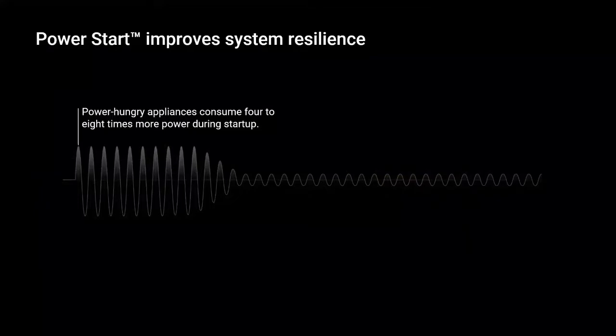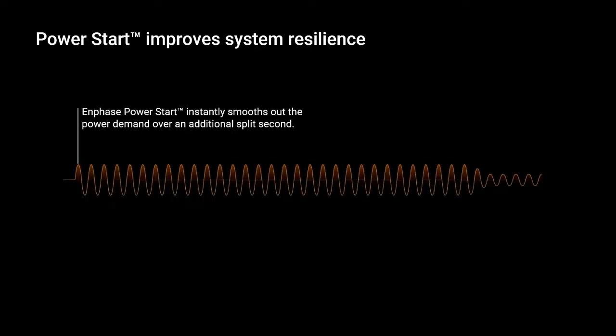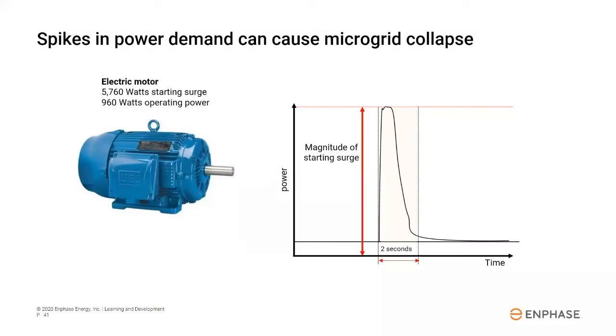Now we're going to talk about a unique feature to Enphase Storage called PowerStart. This is a powerful technology for the purpose of improving the resiliency of the battery backup system when it's grid disconnected. It detects spikes in power demand, which could potentially cause the battery system to shut down, and it smooths them out over a little bit more time to help keep the microgrid up. Significant power demand spikes occur when certain types of appliances with motors first start up, such as pumps, air conditioners, sometimes large fans and refrigerators can even be problems.